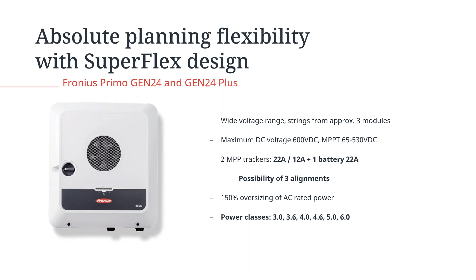So it's also possible to do oversizing on both the Gen24 and the Gen24 Plus. So in terms of the DC to AC ratio, you can achieve a factor of about 150% oversizing. The power classes for the Gen24 and Gen24 Plus are from 3.0 up to 6 kilowatt. When it comes to the Symo version of it, we are also looking at the SuperFlex design capability. Also here we have a wide input voltage, and therefore it makes it possible to start with 3 modules on your PV array. The maximum voltage on the DC side for the Symo version is 1000 volts, and the MPPT operating voltage starting from 80 to 800 volts.